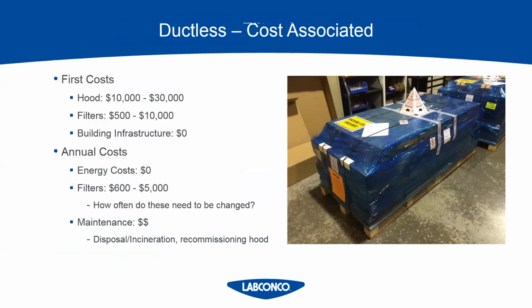How often do they need to be changed? And that's always the golden question, and you have to have a chemical assessment form filled out in order to find out that answer. So we estimate the filter cost to be $600 to $5,000 annually. So quite a range, yes, but we can narrow that down if you give us your application. Disposal would also be included in that cost, which is not included in the $600 to $5,000. So whatever that would cost on top.